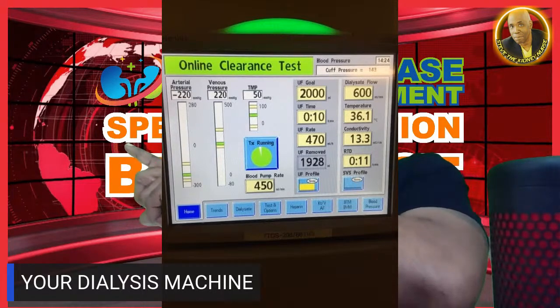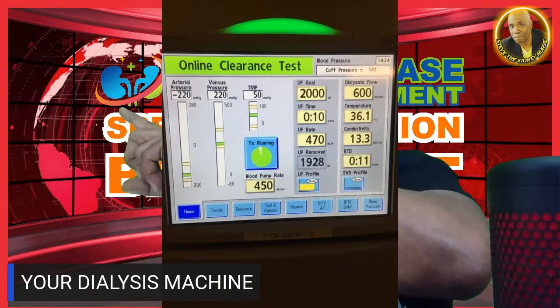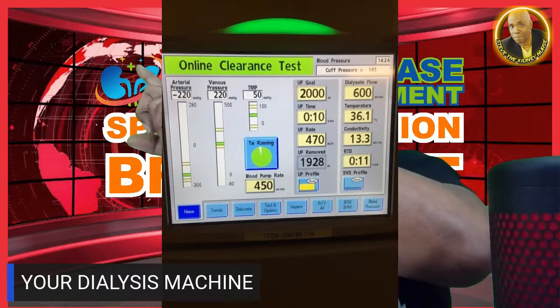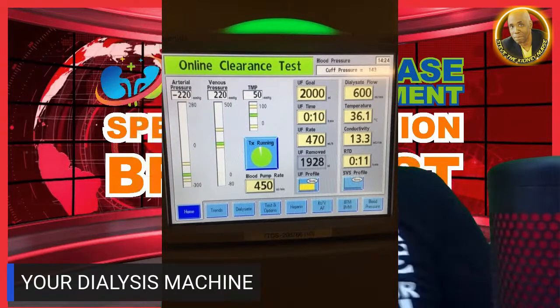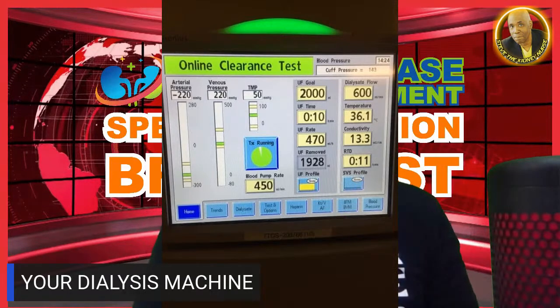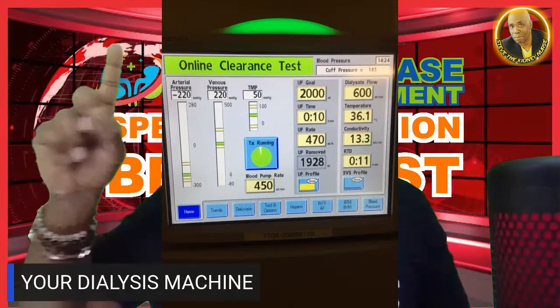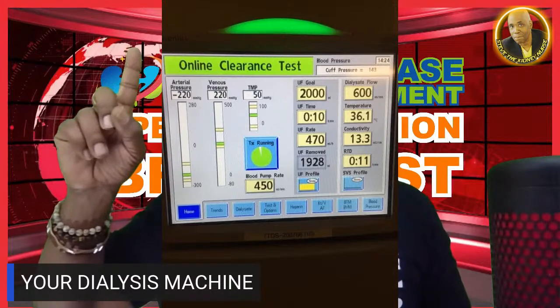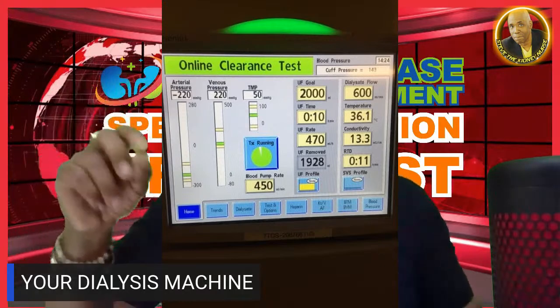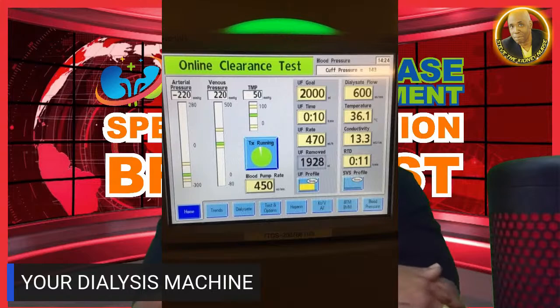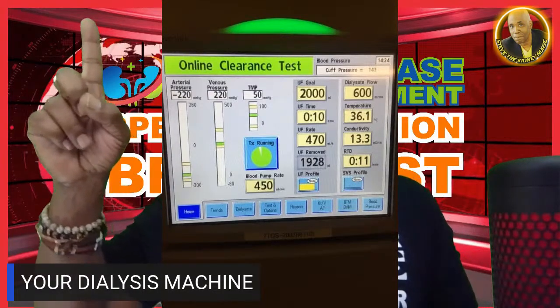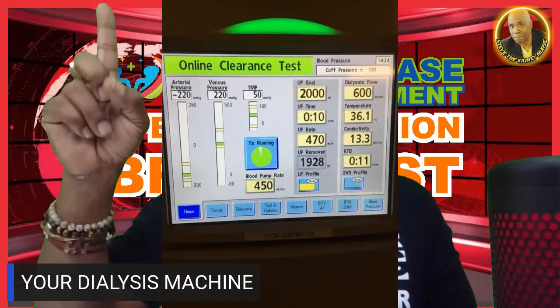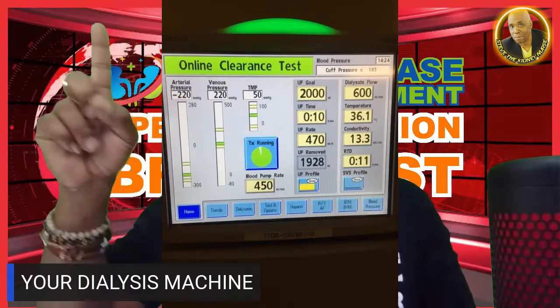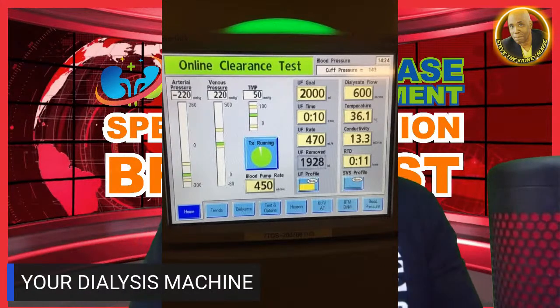Over here where it says RTD, it's your dialysis return time. And then here is the conductivity of the bath. Then you've got the temperature right here, and your dialysis flow rate. Now, let me tell you, some of you warriors, if you're on the machine and you feel cold and it's not like that in the facility, check the machine temperature, because they normally have it set on 35.5, especially if you have low blood pressure, because the lower the temperature, you chill. And when you shiver, it brings your pressure up. So make sure you check the temperature. It's right here on the machine next to the UF time. You can see a little bit of it says temp. They can adjust that on the machine. You can see it on the screen here where it says 36.1.